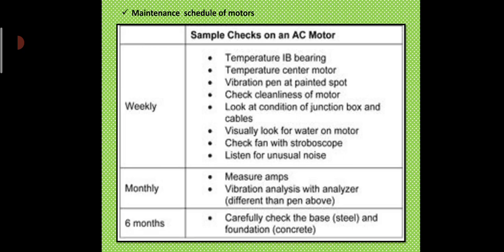Now, the maintenance schedule of the induction motor, synchronous motor, likewise. Like other equipment, if proper maintenance of the induction motor is done, it can give service for a long period without giving trouble. So here are the sample checks on an AC motor, and the frequency of inspection is weekly, monthly, six-monthly, etc. On a weekly basis: check bearing temperature, motor temperature, vibration at pin-point spots, cleanliness of the motor, condition of the junction box and cable, visually look for water on the motor, check the fan with a stroboscope, and listen for unusual noise.